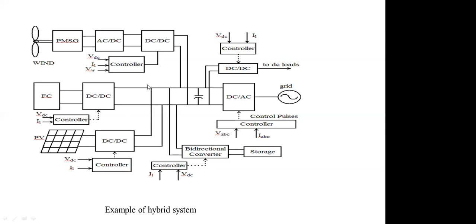Now, when you have a hybrid system, you can operate in isolated mode, grid-connected mode, or islanding mode. There's a difference between isolated and islanding mode. Isolated mode means your system is never connected to any grid - it's always separately operated, completely standalone. Islanding means it's supposed to be connected to the grid, and in case of grid failure, your system has to operate in an isolated or islanding mode. Keep that in mind.